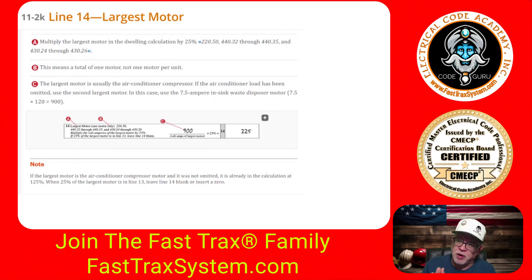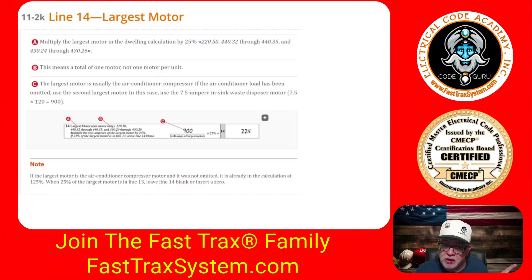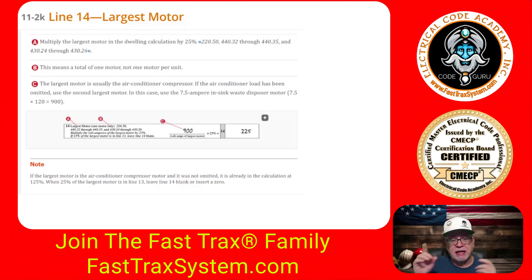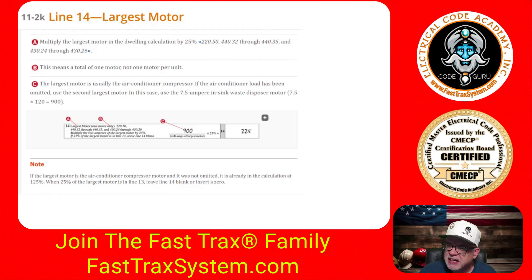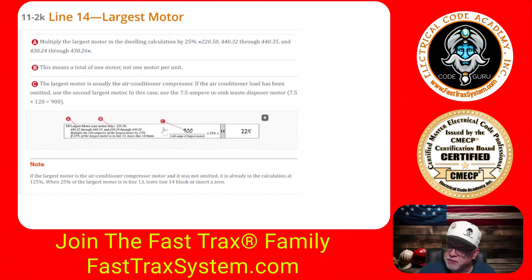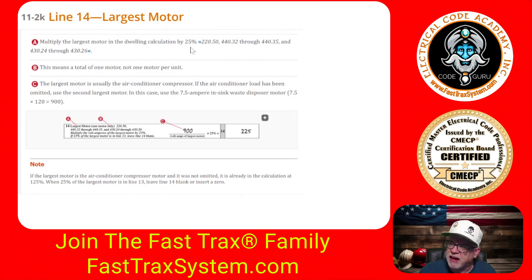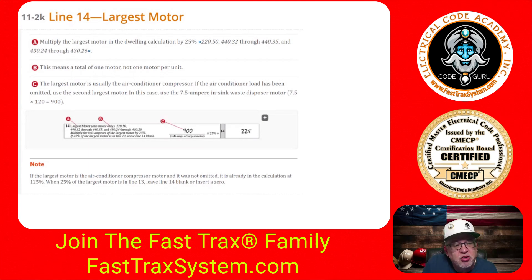Why is it important to say this? Because this is part of Unit 11, which in our program covers multifamily buildings. It would be the same for a single-family dwelling — when we're trying to find the largest motor, it applies in a multifamily dwelling too. We're not trying to get the largest motor in every dwelling unit; we just want the largest motor, period. Our forms give you the form to fill in plus code references. The callout here reminds you to multiply the largest motor in the dwelling by 25%. Does the code explicitly say take the largest motor at 25%? No — so let's look at where we get that.